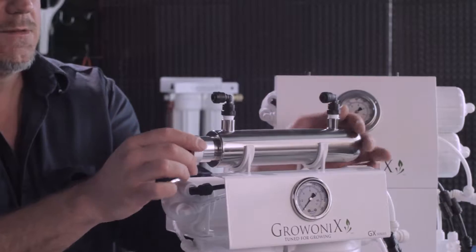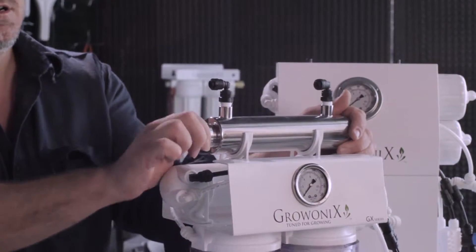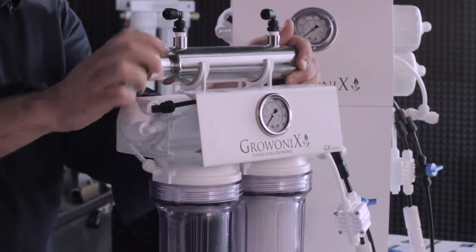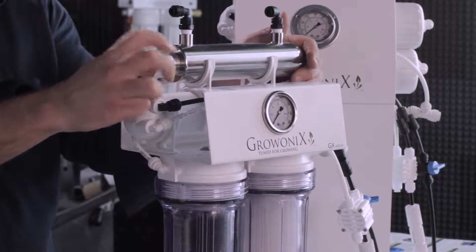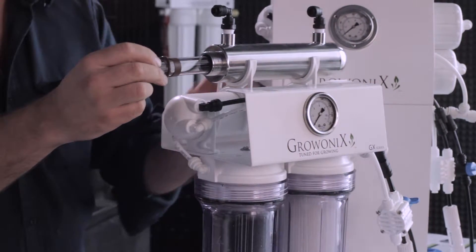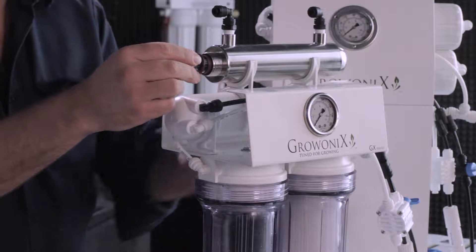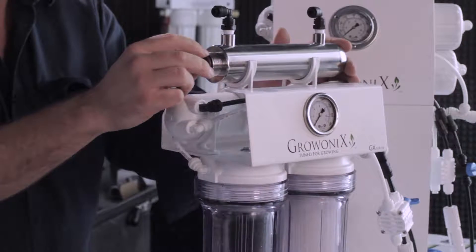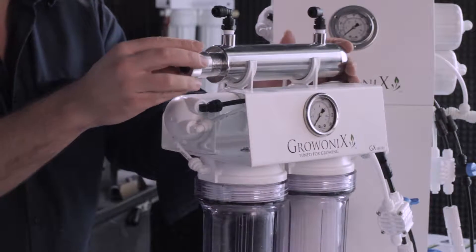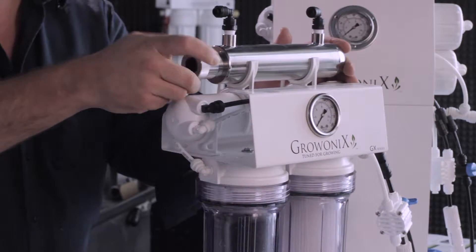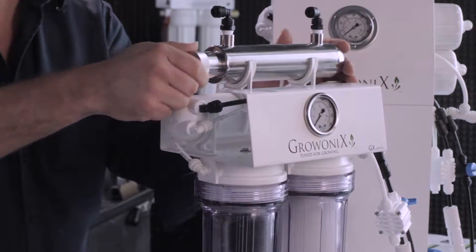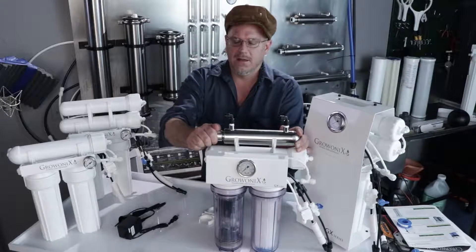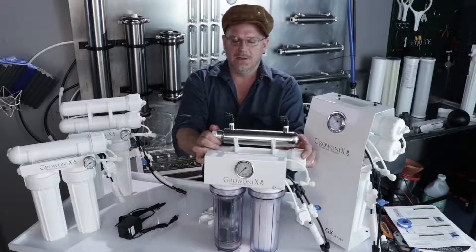The next thing we want to do is make sure the end cap is snug. And I'm going to pull it off to show you what it looks like underneath. The quartz sleeve that houses the bulb is in here. And there is an O-ring. And you want to tighten this thing until you feel the cap touch the O-ring. Right there. And just a little bit more. Not too much. And it's good to go.